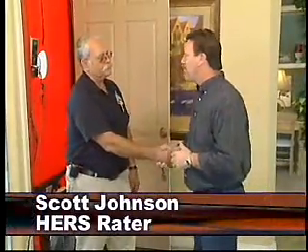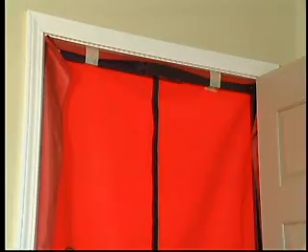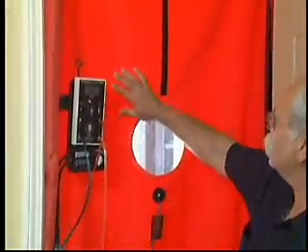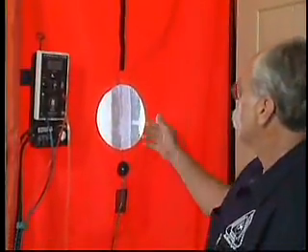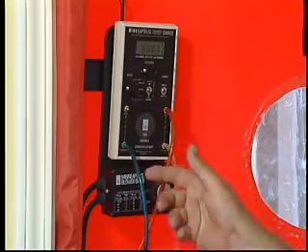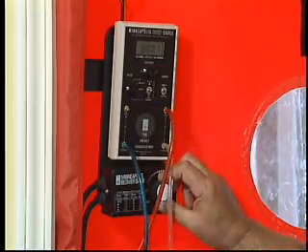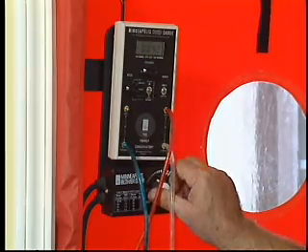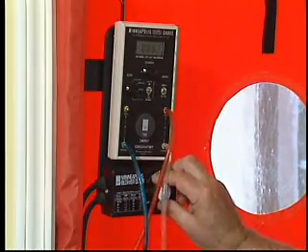And here to tell us how a blower door works is Scott Johnson from Action Now. Hi, Scott. How you doing, Steve? Well, tell me about the blower door and how it works and how you prep to make it work. A blower door is a simple piece of equipment. It's comprised of a frame and a membrane and a fan and a manometer and a speed control. Those tubes coming out of the manometer that hook up into the fan and go to the outside, those are our reference taps to let us know really what's going on with pressures and the airflow itself.